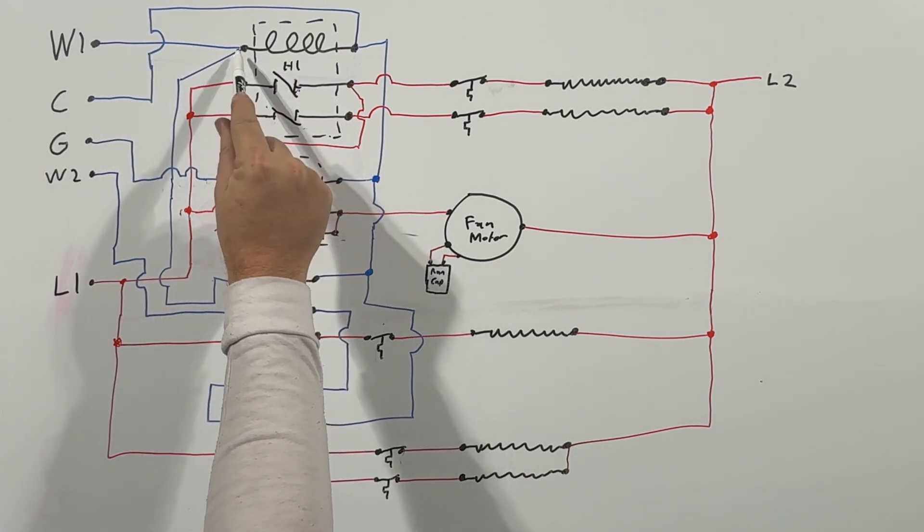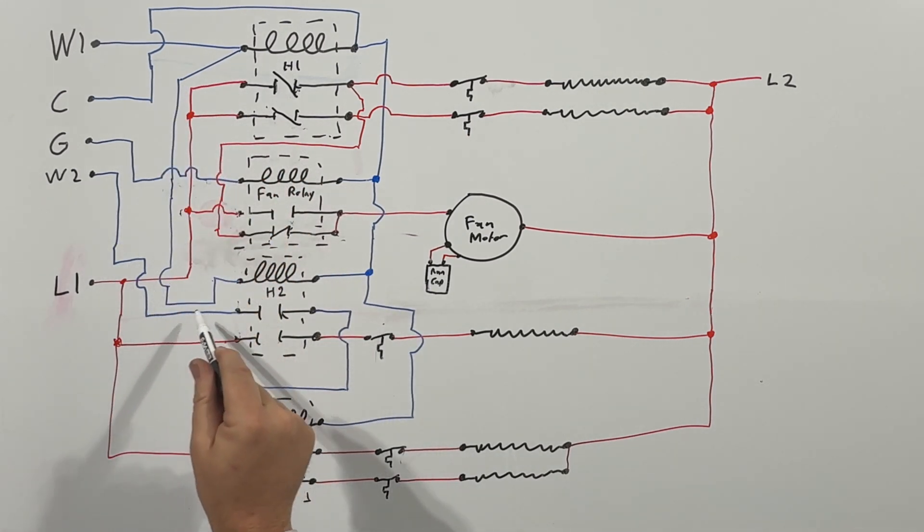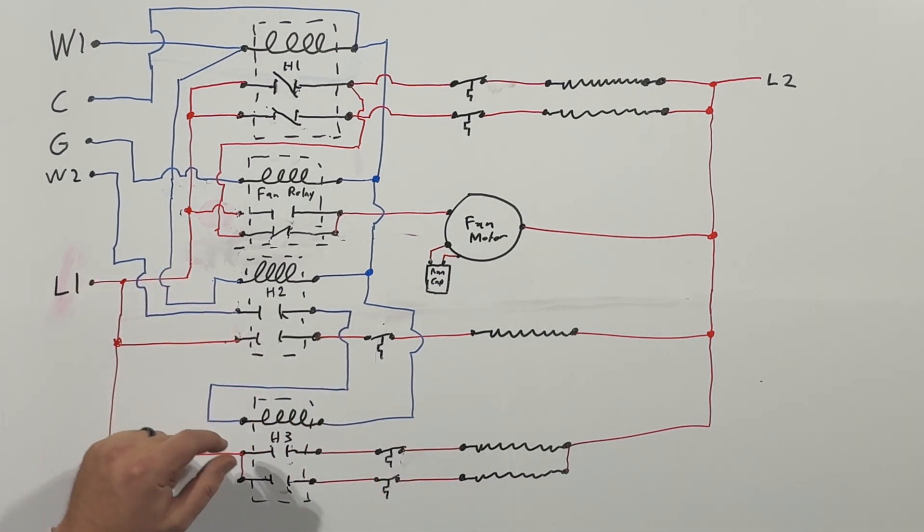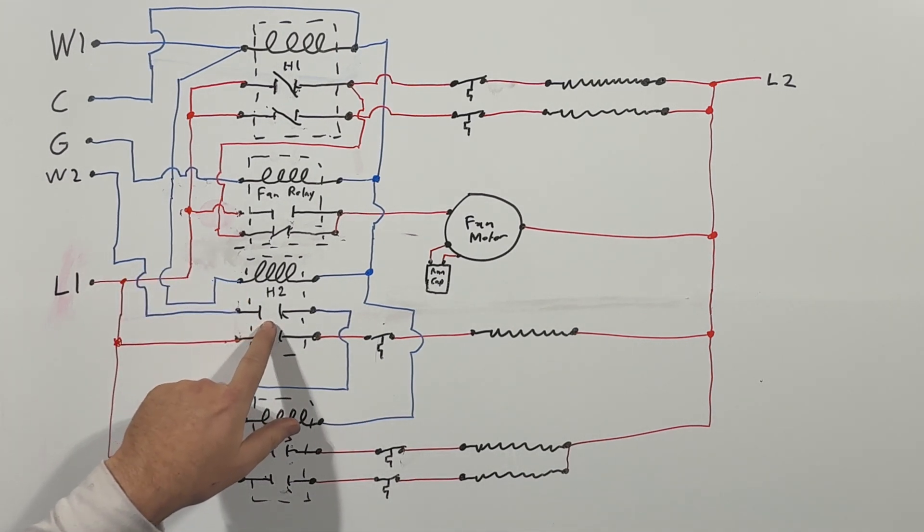Okay, now 24 volts, it's also bounced off, comes out here. So from our W1 it's energizing this one, but then it's also bouncing off, coming down and hitting our second heat relay, H2, energizes this coil.